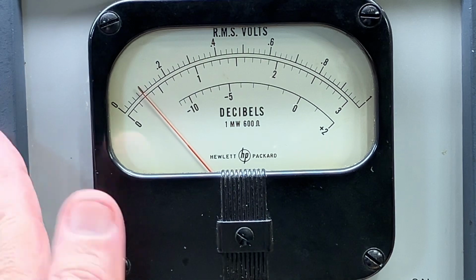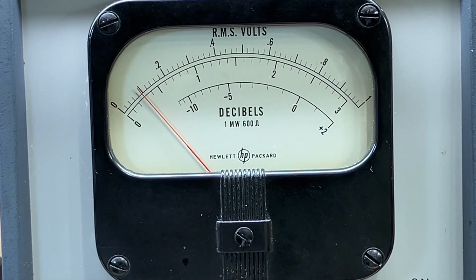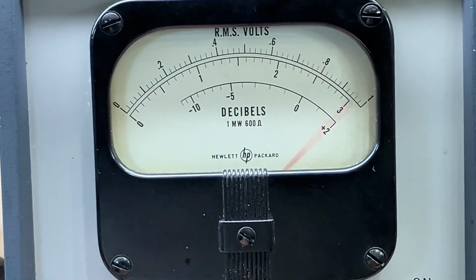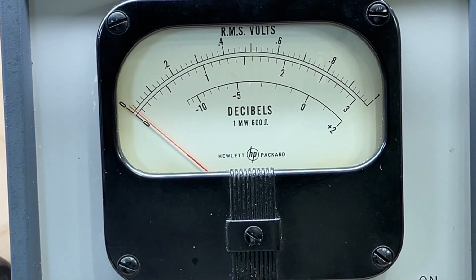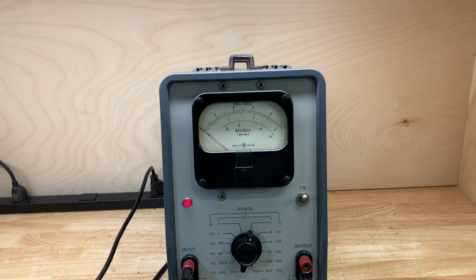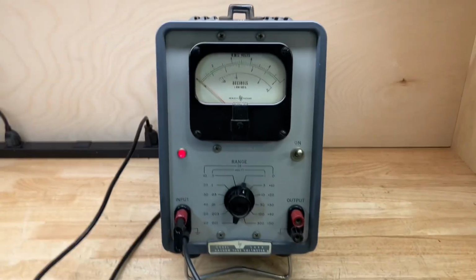The specification for this instrument is plus or minus 2% for the majority of the frequencies. Towards the lower and upper frequency ranges, that tolerance gets wider. But at the 400 hertz level, the tolerance is plus or minus 2%. So all of those ranges read within 2%, so the instrument is in spec. It also passes all the frequency ranges, but I'm not going to demonstrate all of those right now. So let's zoom my camera back out. We have the completed 400D.